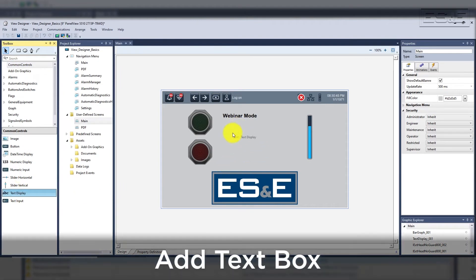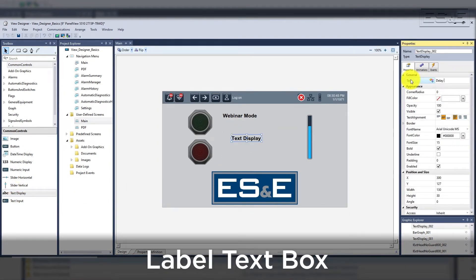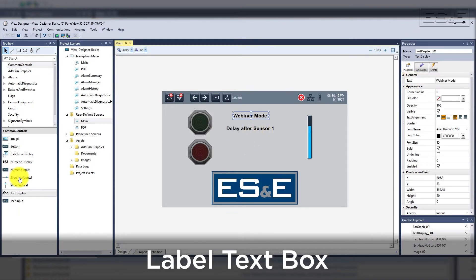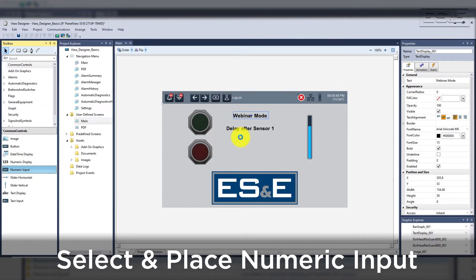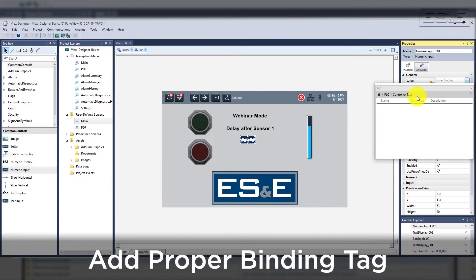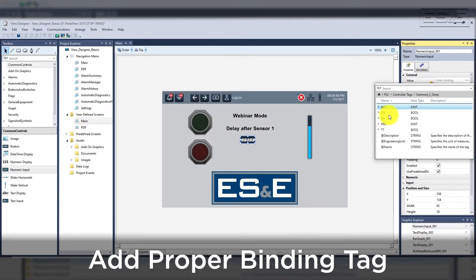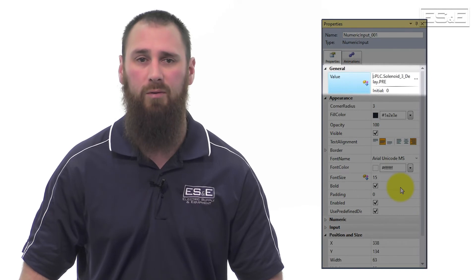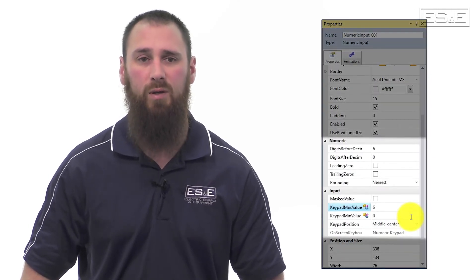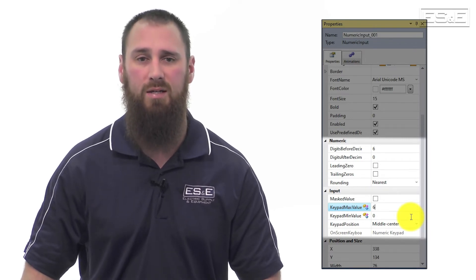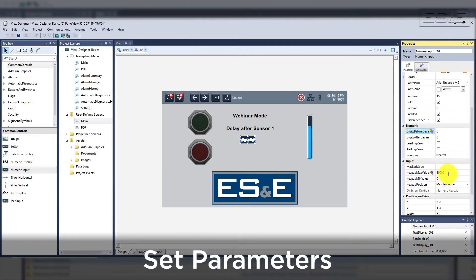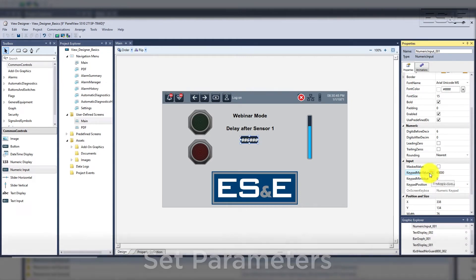The next item we will add to our screen is a numeric input to change the time delay after sensor 1 is no longer active. First, we will add a text box to label the input — the label will be 'delay after sensor 1.' We will use a numeric input from common controls, select it and drag and drop the object on the screen. We will bind the value tag which will show and edit the same tag. We need to search for the timer on instruction tag and then pick the preset tag. After the value is bound, we need to configure how we will enter and view the value along with the min and max values allowed. Let's set the limits from 0 to 60,000, which is 60 seconds. You could tag it to a variable also instead of hard coding the value in the project itself.